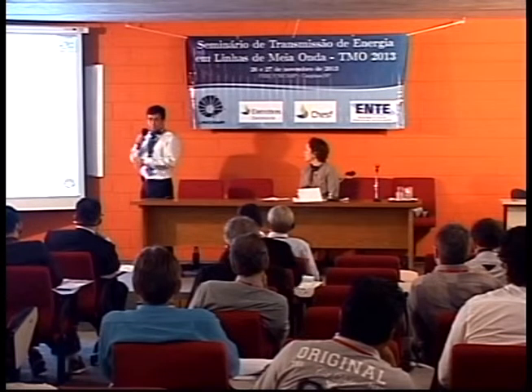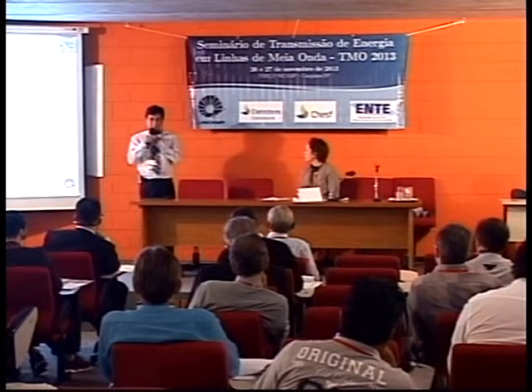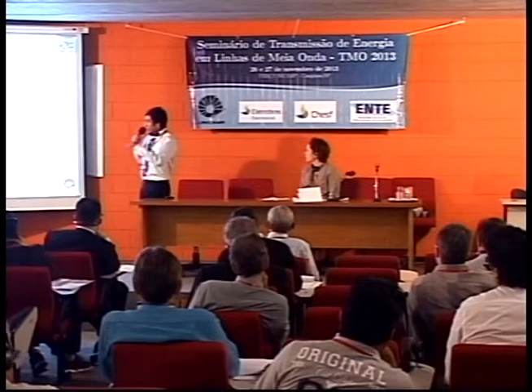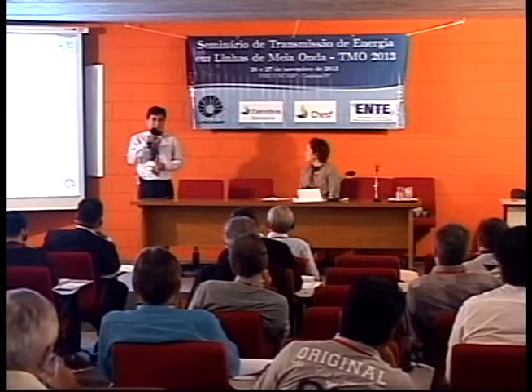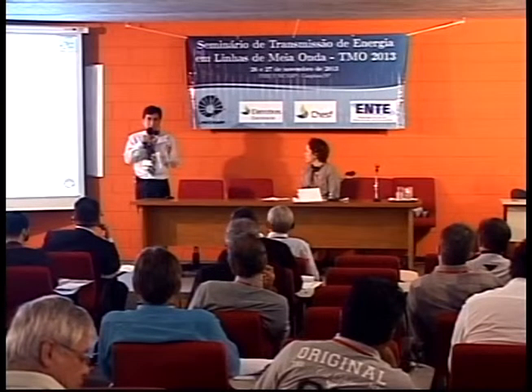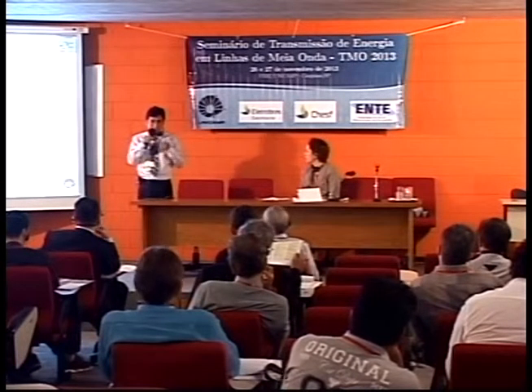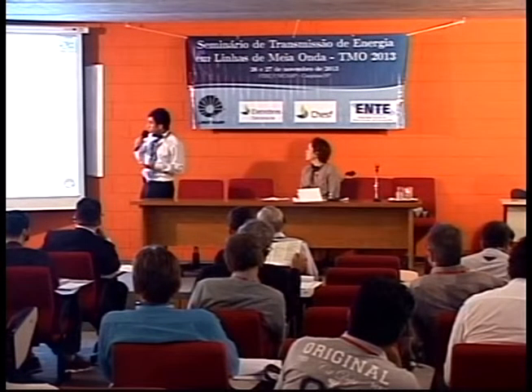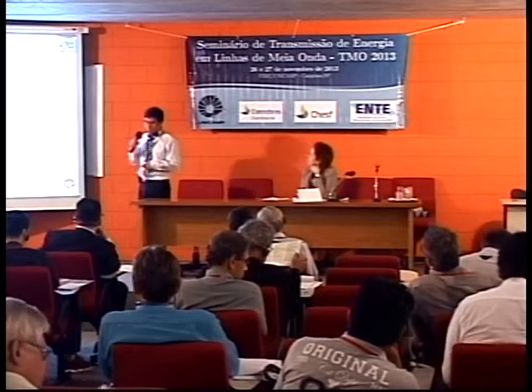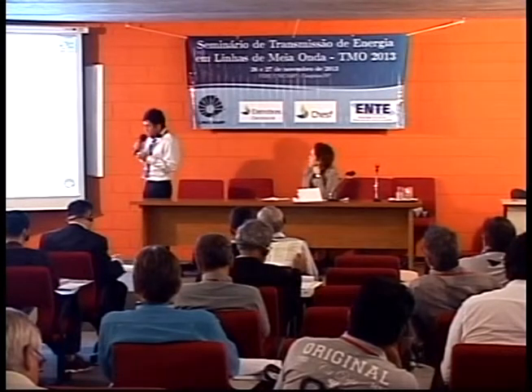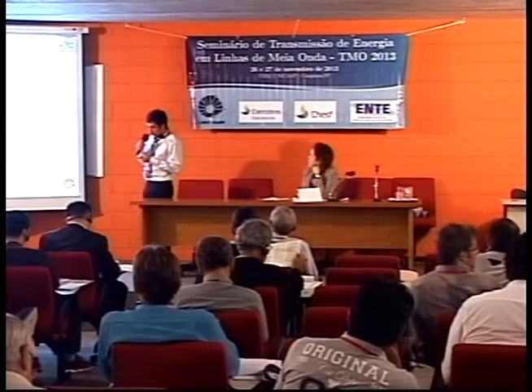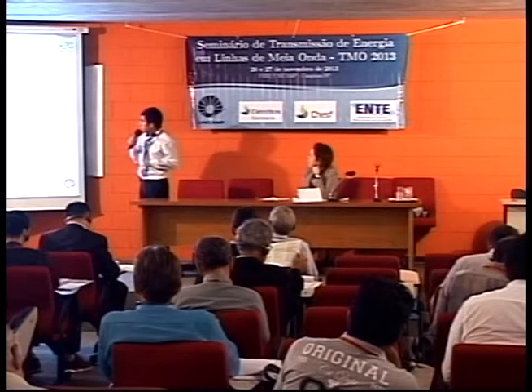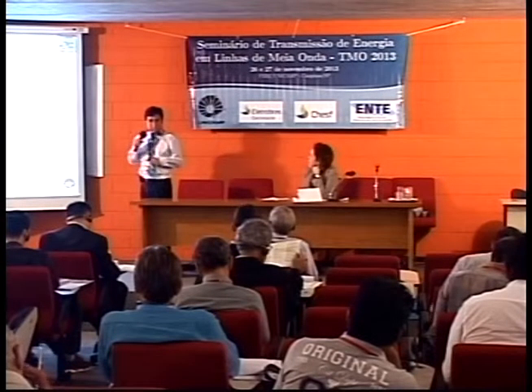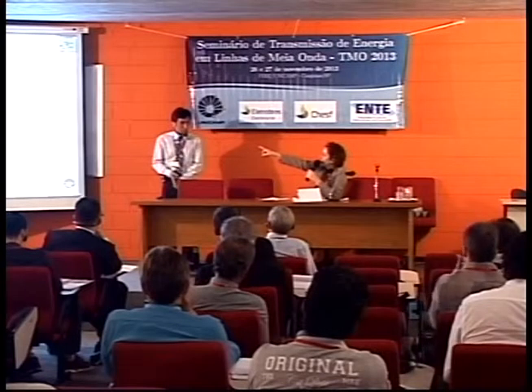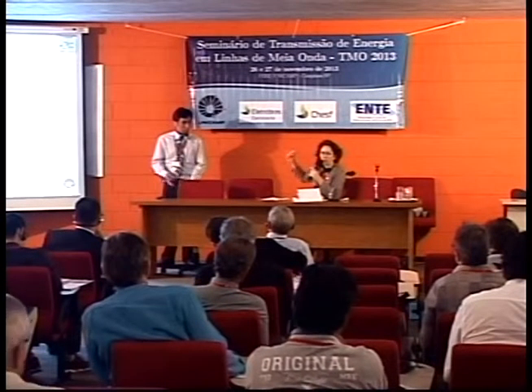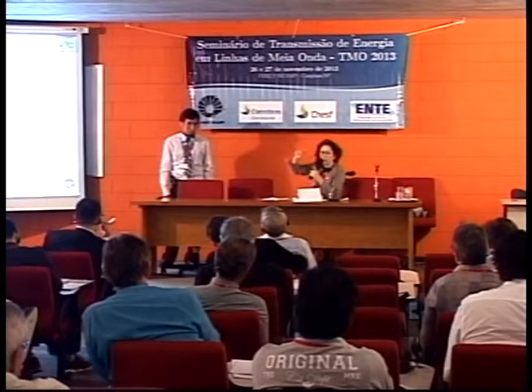The case of the work and the project is based on the energization test. Here there are many more problems than that. We have no load, which is a constant. In the real system, we would have load variation and would have to develop specific protection, and there are many more considerations than what is shown here. It was shown that there is difficulty identifying faults in the protection of the line and its operation. So actually you cannot close the middle of the line without having communication between the substations. So you have to have information.